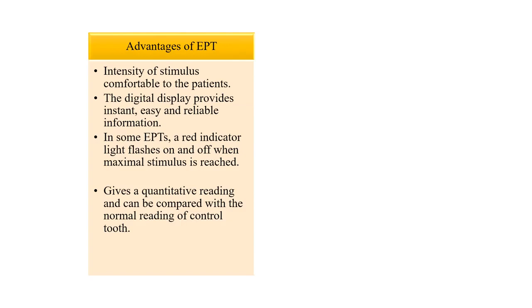The distinct advantage of electric pulp tester is that in heat and cold tests, there is a specific temperature of the media used to assess pulp testing. So you can't vary the temperature much. In case of electric pulp tester, when you suspect that there is irreversible pulpitis, even a low stimulus will elicit severe pain in the patient. Therefore, in electric pulp test, we can start with a lower intensity current, and once a positive response is elicited, we don't need to go any higher to cause patient discomfort.